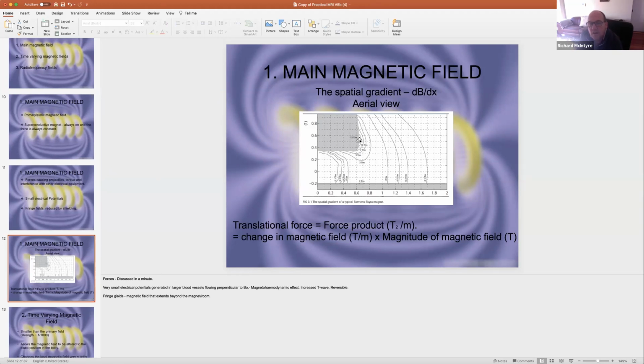Okay, so we know that the higher the spatial gradient, the more force on that aneurysm clip. So if that aneurysm clip went around this area of the magnet, there's a chance it would pull off the blood vessel. Okay? So it's very important that if it was an urgent scan and we had to keep the patient in and they had an aneurysm clip, this aneurysm clip only stayed in the very middle of the magnet, okay? Or put it on another magnet that has maybe a maximum gradient of 10 Tesla per meter, okay? If that aneurysm clip had a maximum field of 10 Tesla per meter.